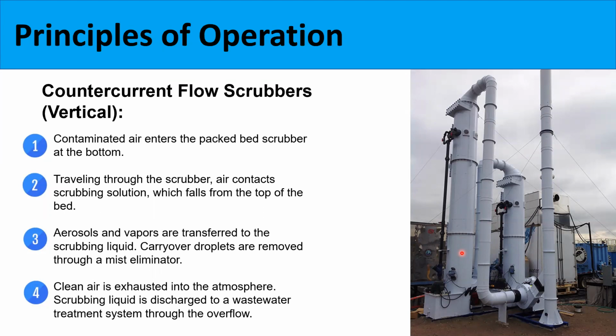Additionally, the scrubber is provided with an entrainment separator, whether it's in the form of packing, chevron blades, or a mesh pad assembly, to capture any entrained liquid droplets in the gas stream prior to discharging from the unit.